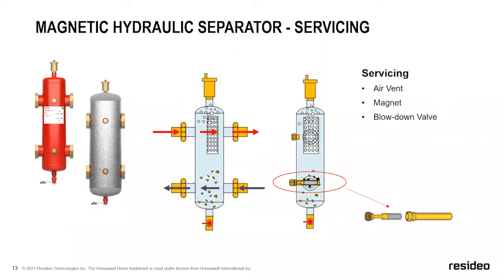From the serviceability standpoint, there's not a whole lot of moving parts. So it is a somewhat expensive product. However, there's not a whole lot to falter on this. Since it's basically a giant tube, there's only a couple of things you need to pay attention to from the service standpoint. First is our air vent up here at the top. This is the point where the air bubbles are going to collect. It works just like that SuperVent. So this air vent will over time fail.